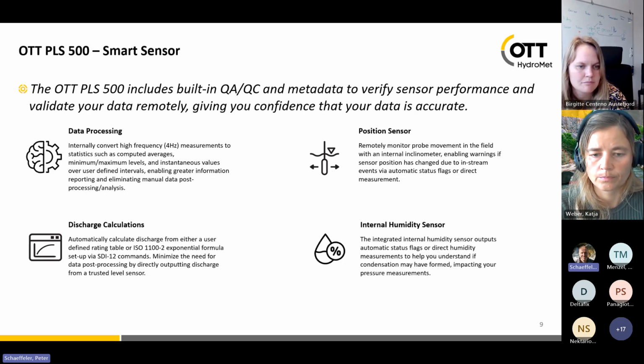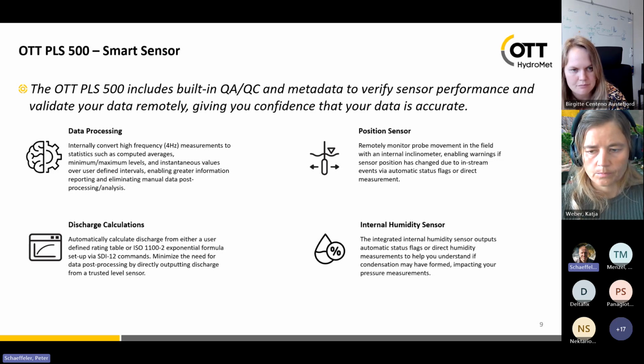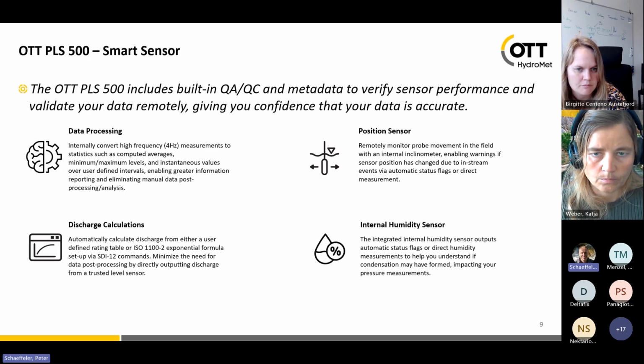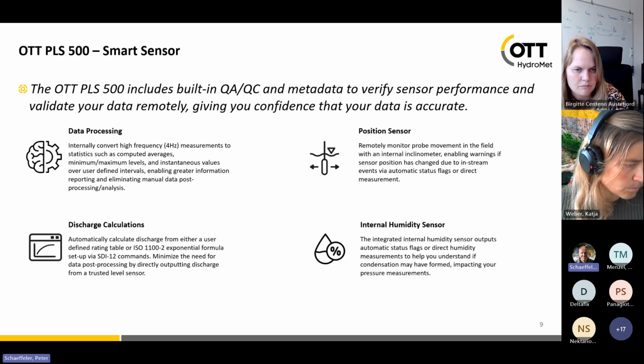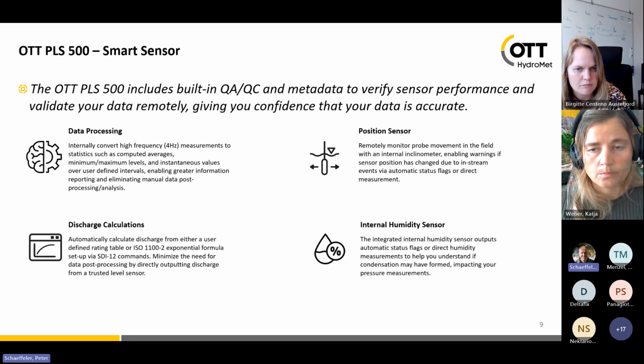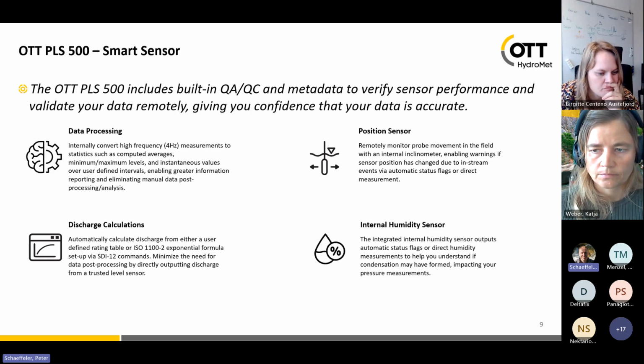The discharge calculation is possible in the sonde. You can calculate discharge from a defined rating table. One comment here, if you do that with a NetDL, for example, I would recommend to do it in the data logger and not in the sonde. It can be done in the sonde, but you have to set up this via SDI12 commands, which is a little bit more cumbersome than just importing, for example, a rating table in a NetDL. You cannot do this the same here in the PLS 500. You have to type in those values, this table, via SDI12 commands, but it is possible.